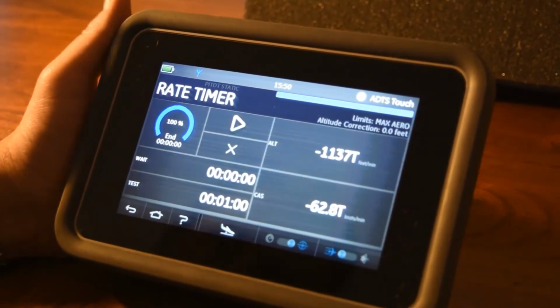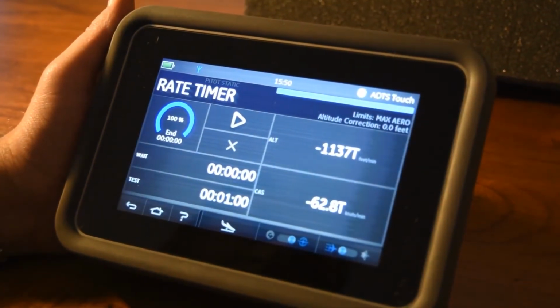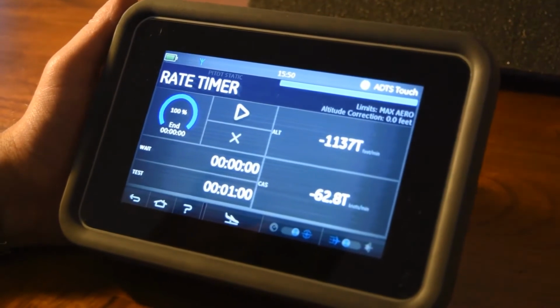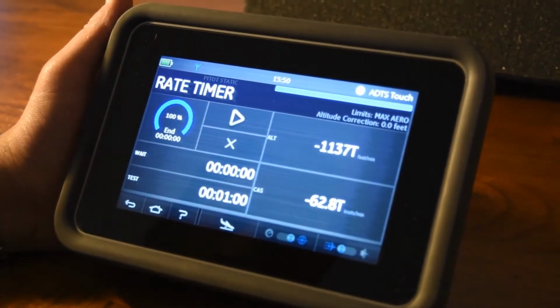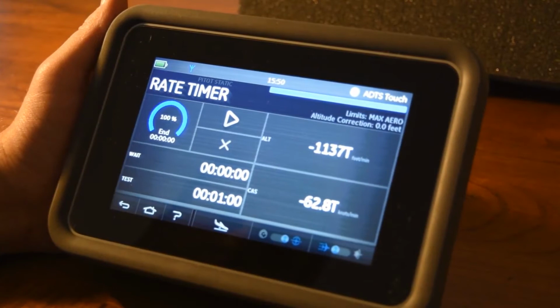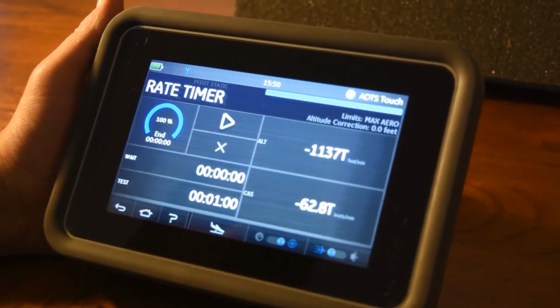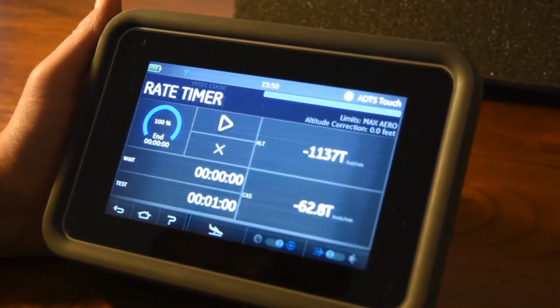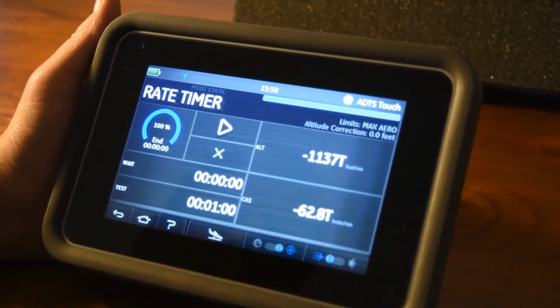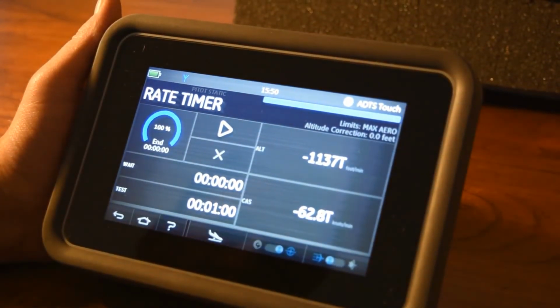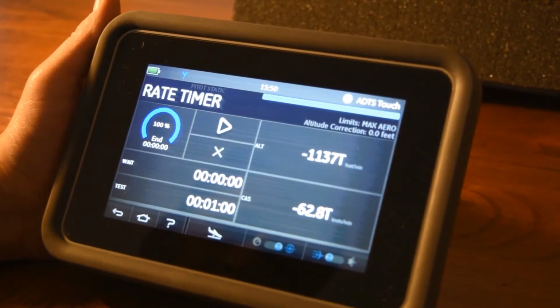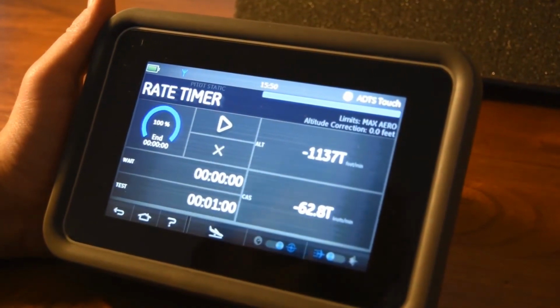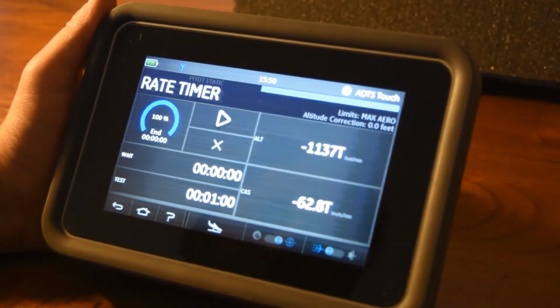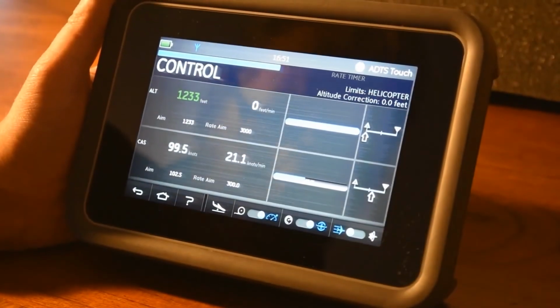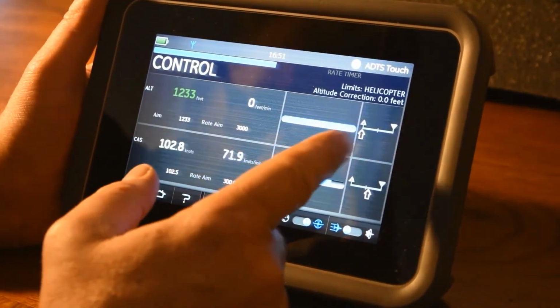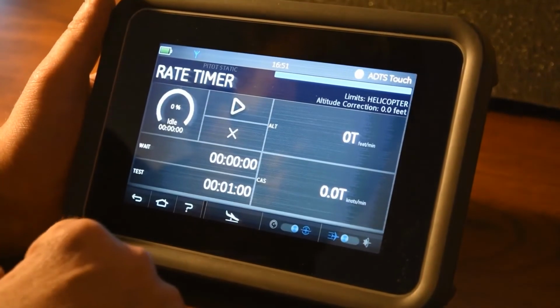Next question everybody asks is, how big a leak can it control? The simple answer is, well, if it did manage to get to the set points that you require, obviously with the leak, it can control that leak. Therefore auto leak recovery kicks in very fast, and I'll try and demonstrate that a little bit later on. Okay, so there's my leak test, and I think I've got a serious problem, and I'm going to try and fix my leak now. Okay, so we just did a leak test. As I mentioned before, my system's got quite a big leak.